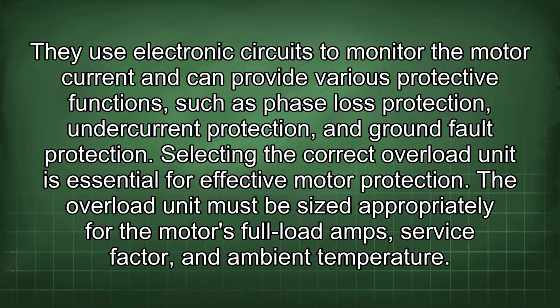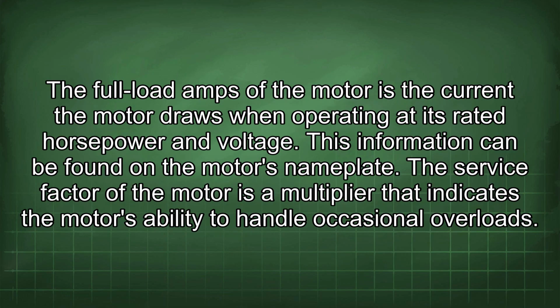Selecting the correct overload unit is essential for effective motor protection. The overload unit must be sized appropriately for the motor's full load amps, service factor, and ambient temperature. The full load amps of the motor is the current the motor draws when operating at its rated horsepower and voltage. This information can be found on the motor's nameplate.